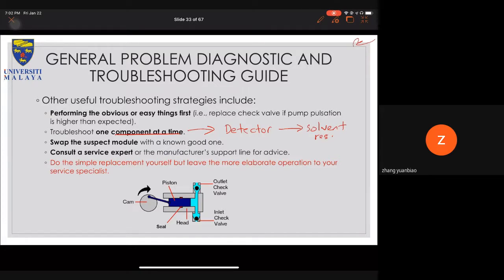You might also, if your company has extra modules, swap the suspected module with a known good one. So if you have two machines, for example, and one machine is currently used and one is not, and the machine that you want to use has a problem, you might want to try and swap the module and see if the problem goes away. If it does, then you can suspect that there's some issue with the module, regardless of what the issues are, but you know that the module is the primary culprit in your problem.